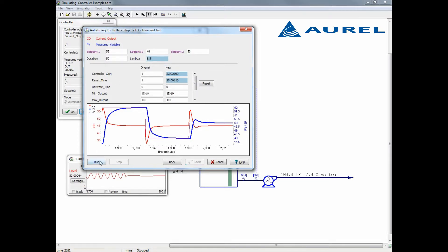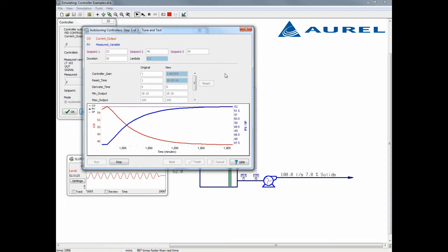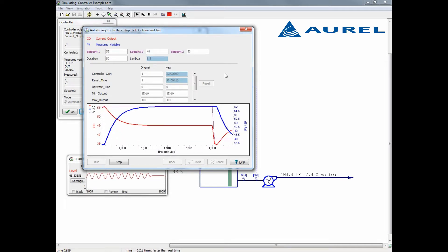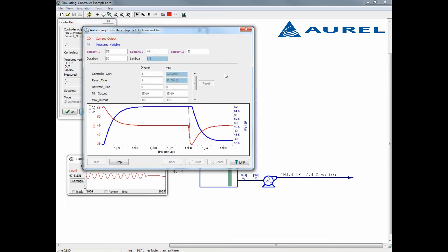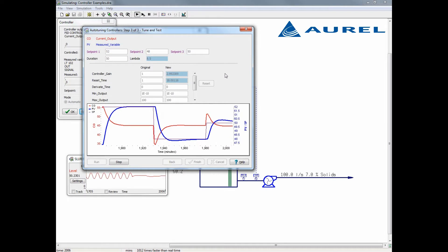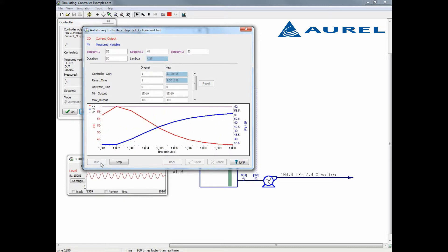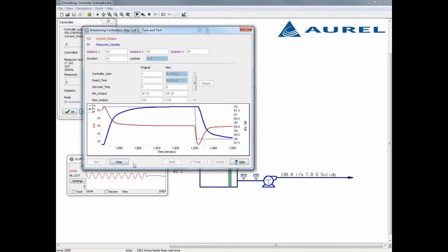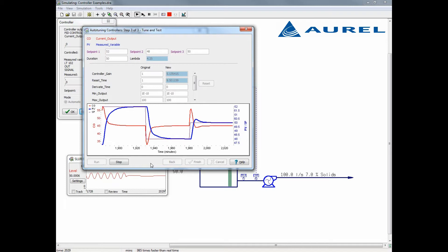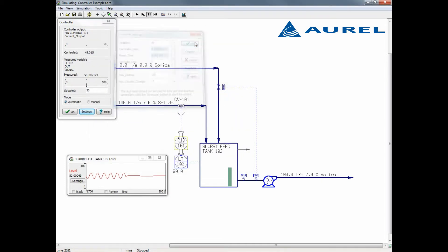To demonstrate this, I can double the lambda value, which will make the controller slower acting. This could be useful if the tank periodically experiences flow surges out from the tank but we still want a steady flow of pulp into the tank. In this case, I am satisfied with the suggested value. I will select finish and our controller is ready to operate.